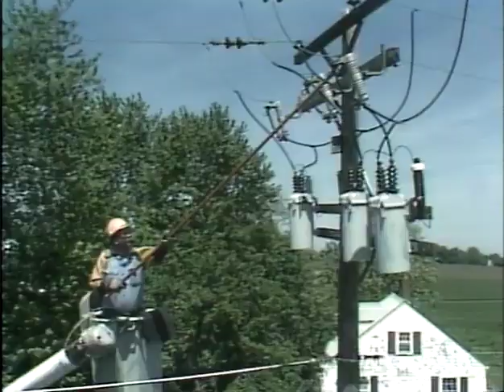Remember that no-load switches must be operated in sequence. In other words, they should be opened only after a circuit breaker is operated to de-energize the circuit, and closed before the circuit breaker is operated to energize the circuit.